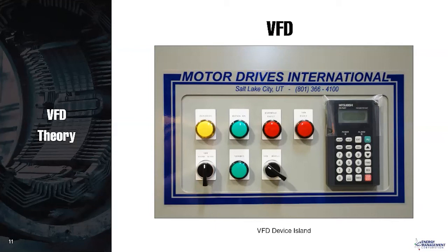So we give you lights. You can see the light on the left says power on. And so when that's on, the power's on. When it's off, the power's off. And I think pretty much anybody can understand that. We have red lights for VFD fault, VFD run, green lights for the VFD running and bypass, and they're all just clearly labeled. And then you have some switches for your hand-off-auto and your bypass.